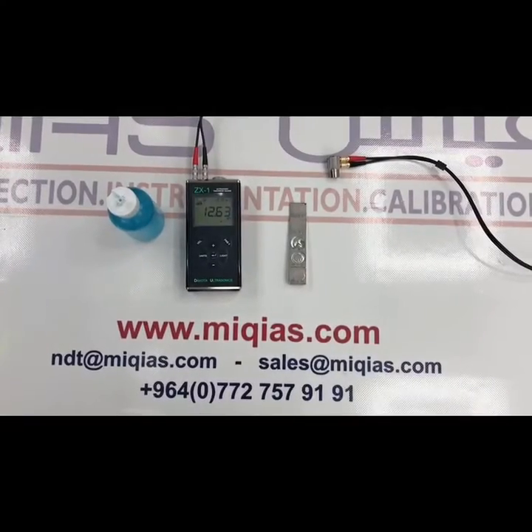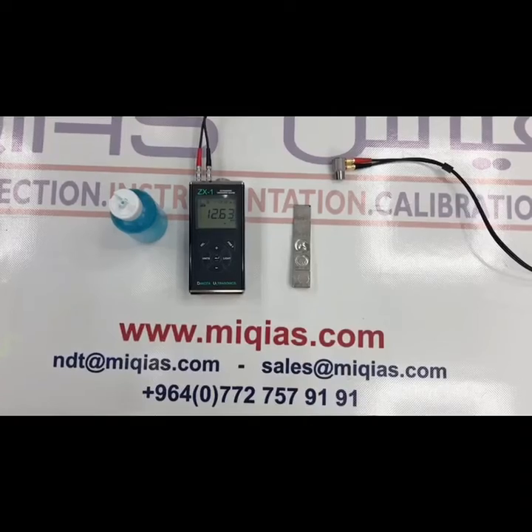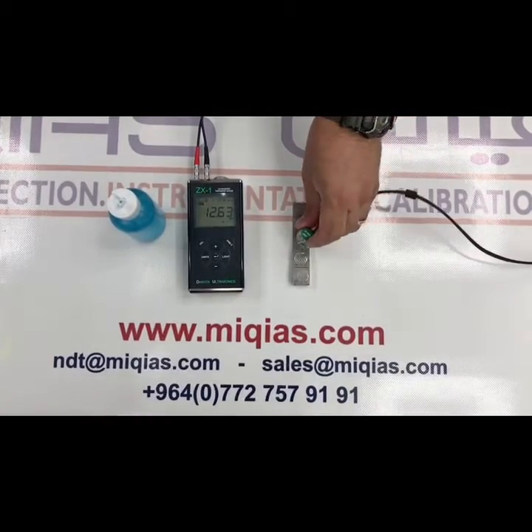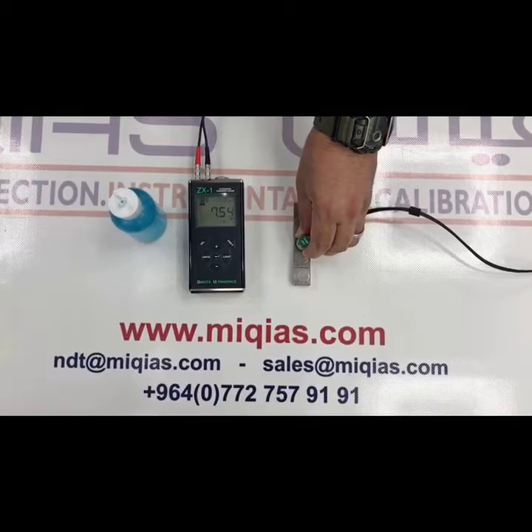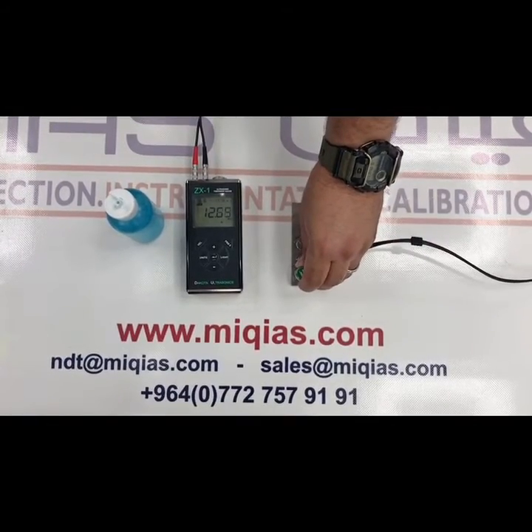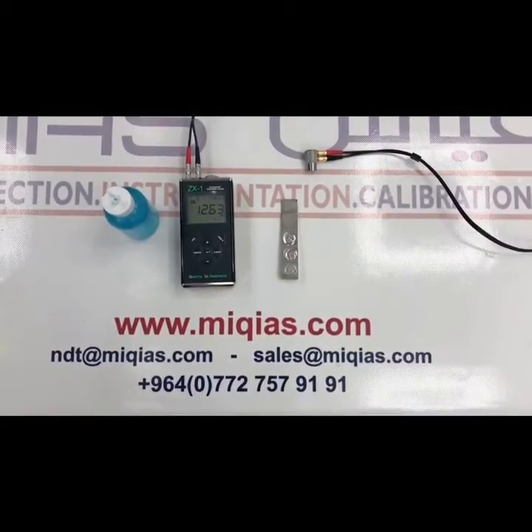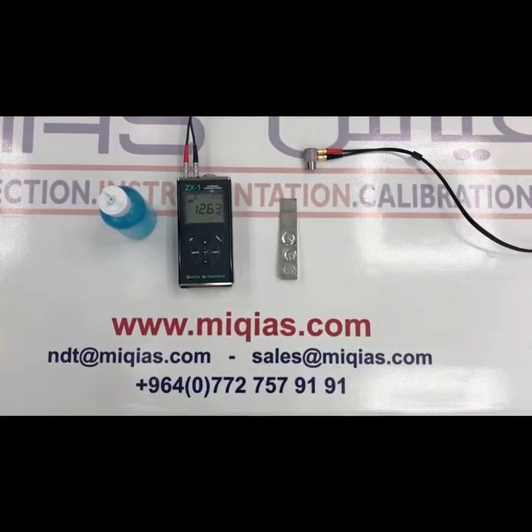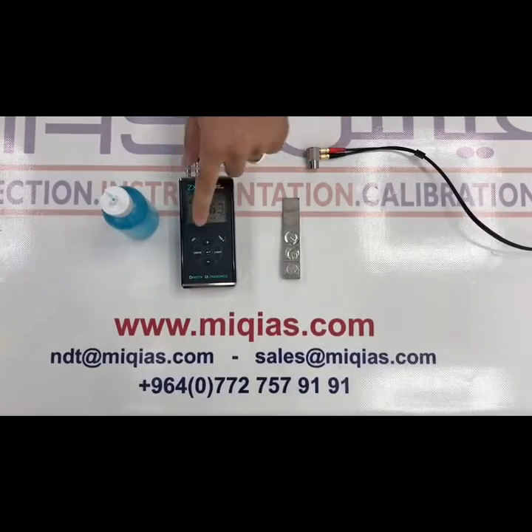Then you can go through checking thickness by putting the probe on the calibration step block. In order to get a more accurate result you can change the velocity by pressing on this button.